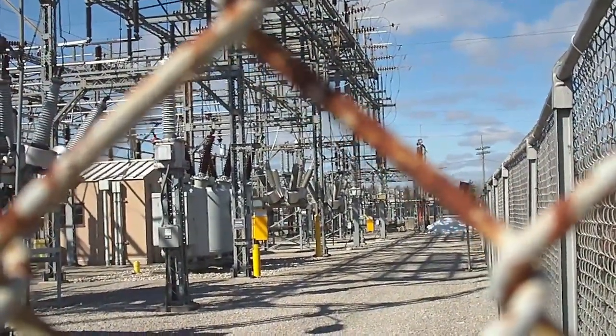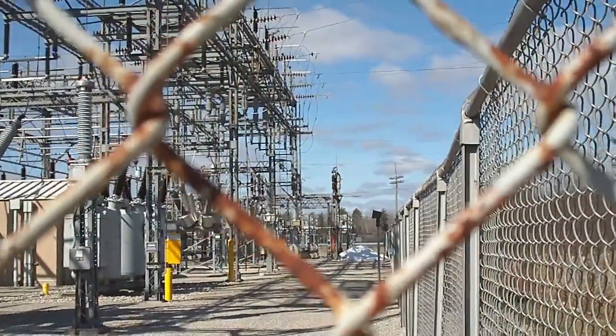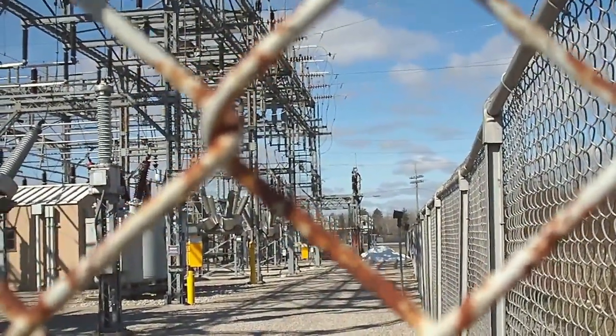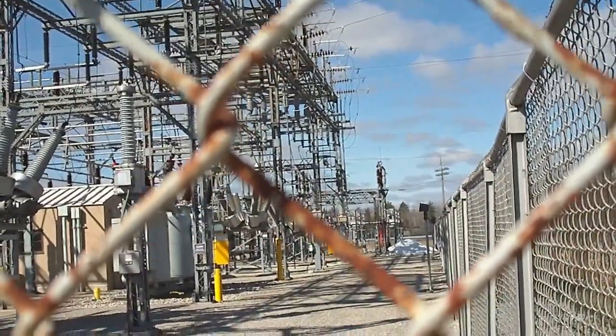The difference is that on the oil circuit breakers, the contacts are bathed in oil, and that's what extinguishes the arc, whereas the SF6 uses sulfur hexafluoride gas to extinguish the arc. They can be considerably smaller.